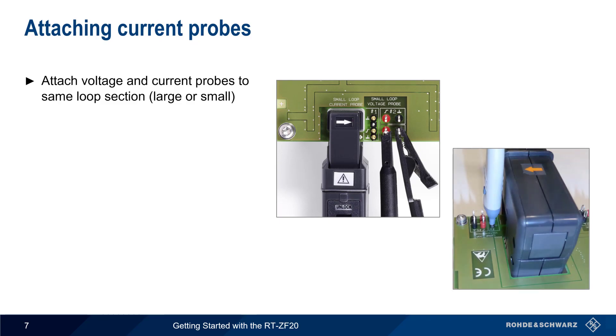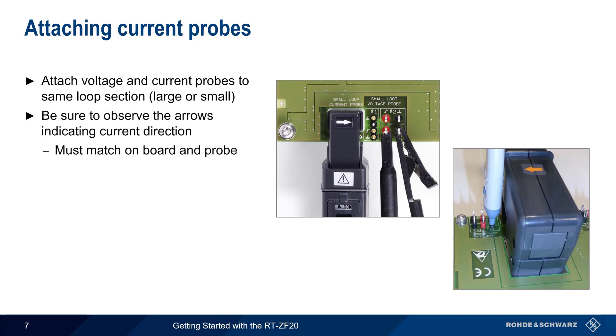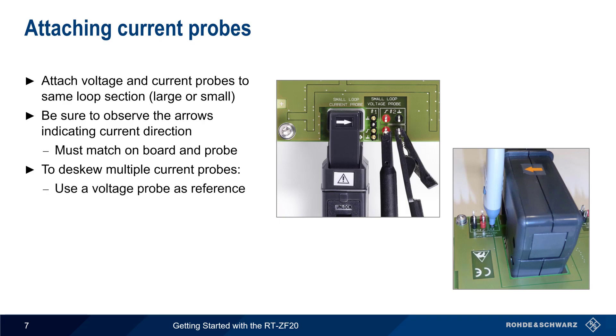When de-skewing a combination of voltage and current probes, these must all be attached to the same loop section as shown. The current probe should be clamped through the opening such that the arrows indicating current direction are the same on the probe and on the fixture. Each loop section has only a single current probe attachment point, so in order to de-skew multiple current probes, a voltage probe should be used as a reference, and each current probe is then individually aligned with the reference voltage probe.